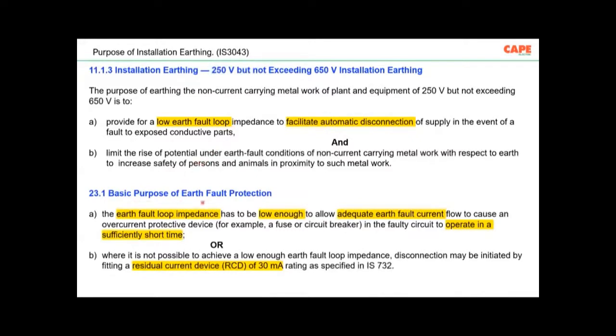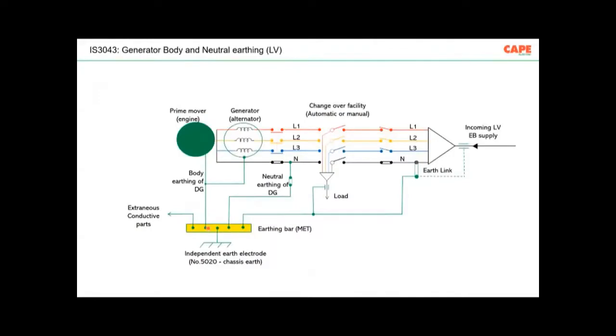Now, if you look at the clause number 23.1, basic purpose of earth fault protection. The earth fault loop impedance has to be low enough to allow adequate earth fault current to flow to cause an overcurrent protective device to operate within a sufficiently short time. What this part says is, in a normal installation, earth fault protection is achieved by disconnecting a protective device, which is nothing but a fuse or an MCB. Similarly, where it is not possible to achieve a low enough fault loop impedance, the disconnection is achieved by an RCD. So these conditions are very well explained in this standard.